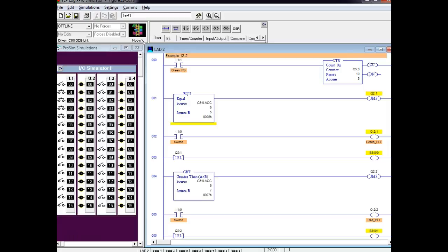A guy was in there working on one of the doors, and they had it locked out and disconnected, and he wanted to push the cylinder out, and the guy went down there and pushed in the wrong relay and closed the other door. They brought him out of there in 2 pieces. So be careful when you force this.